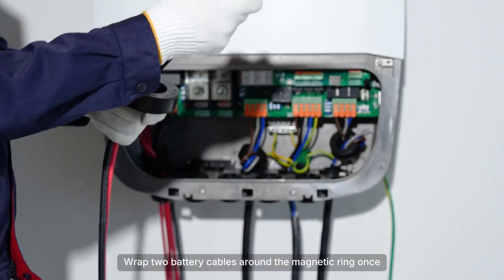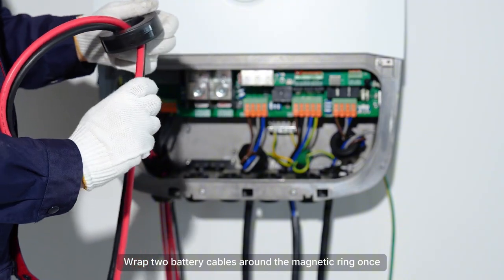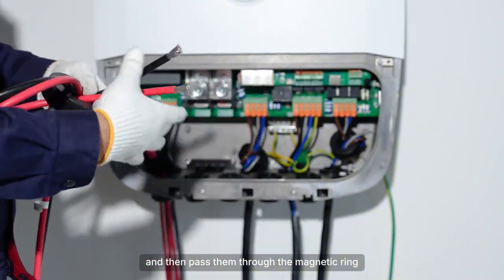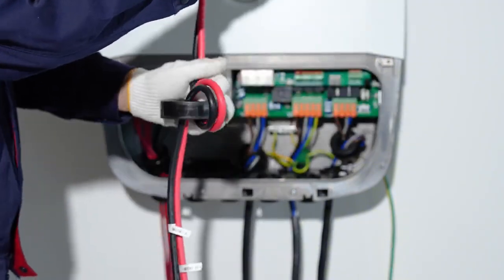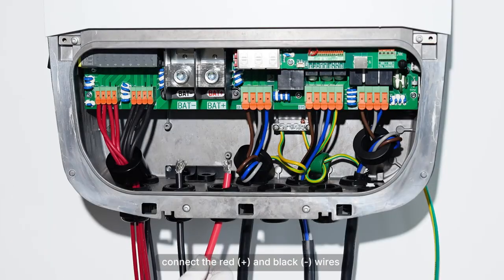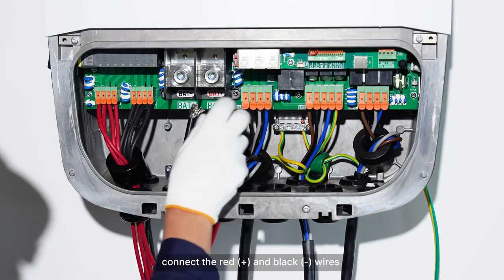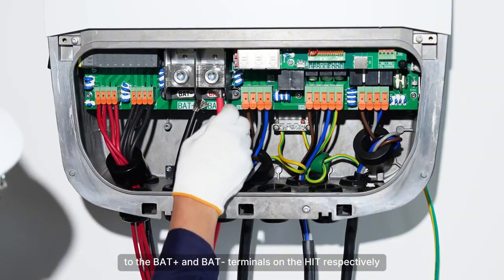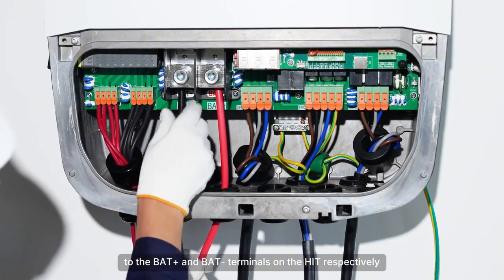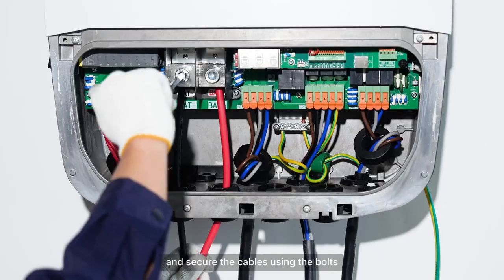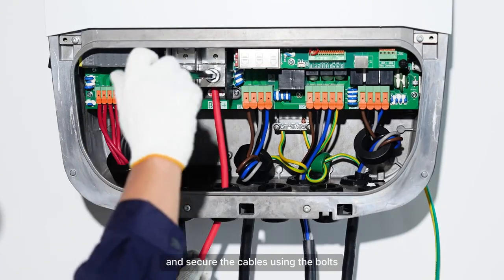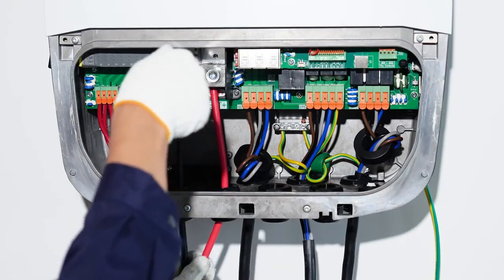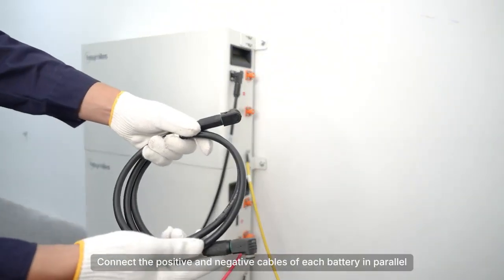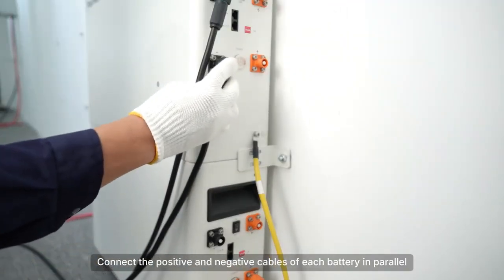Wrap two battery cables around the magnetic ring once, and then pass them through the magnetic ring. Connect the red positive and black negative wires to the bat positive and bat negative terminals on the HIT, respectively, and secure the cables using the bolts. Connect the positive and negative cables of each battery in parallel.